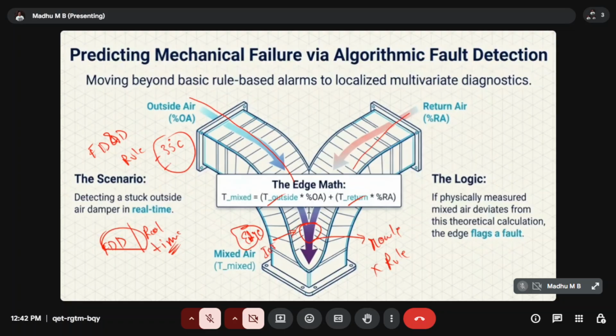It will keep on monitoring this temperature. Now if it senses that something is not right as per the historical data, it will take the necessary action without manual intervention. It could be opening the dampers or closing the dampers. These kinds of actions we can process at the edge itself, instead of sending the data to the centralized processor in the data center and then giving back the command to the damper to open or close. So we are trying to reduce the latency here, and we are trying to immediately take the mechanical decision instantly.